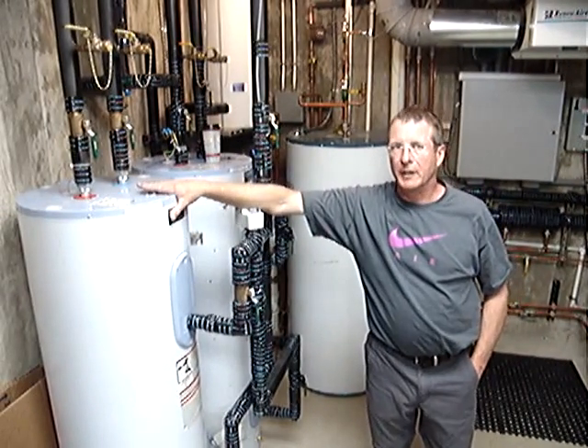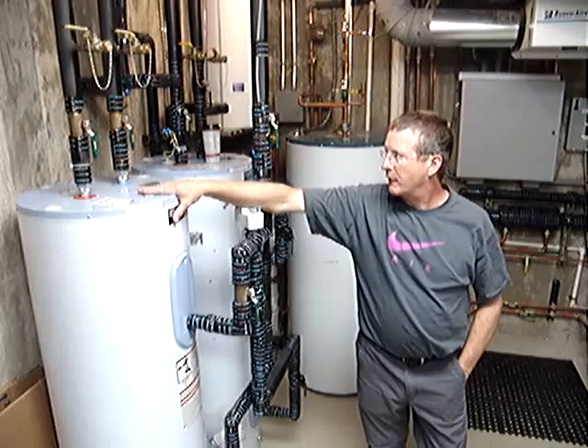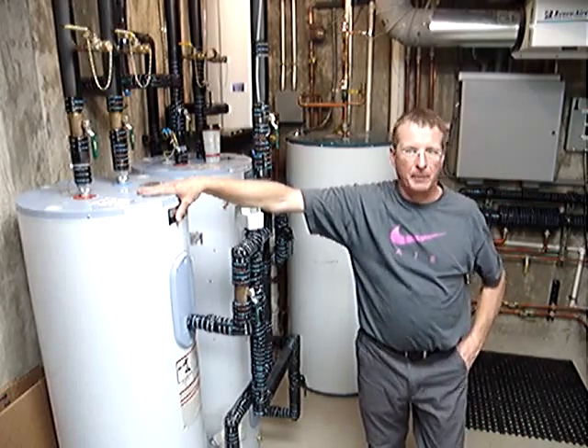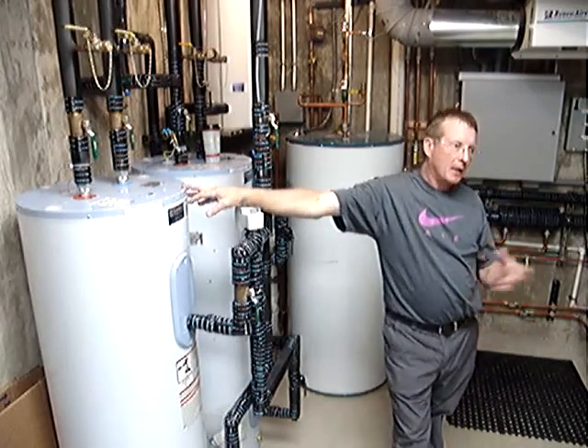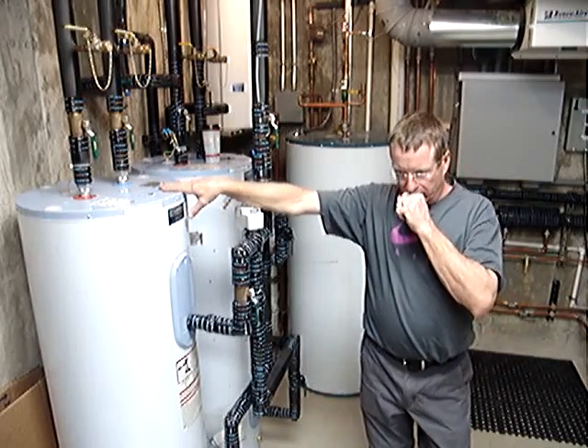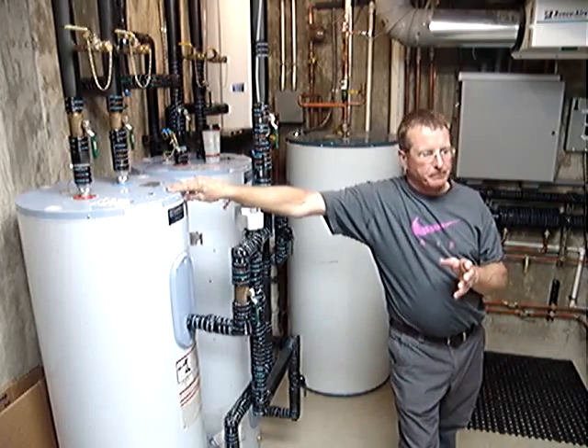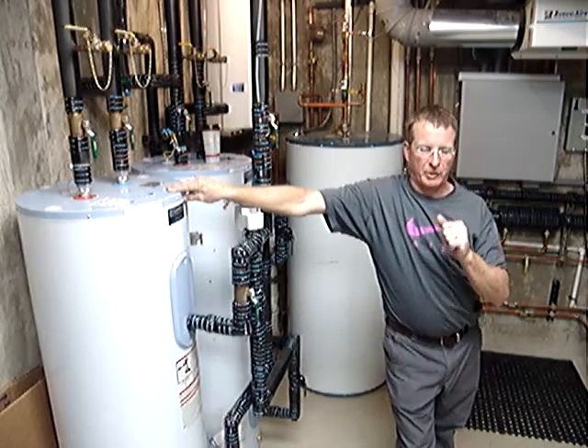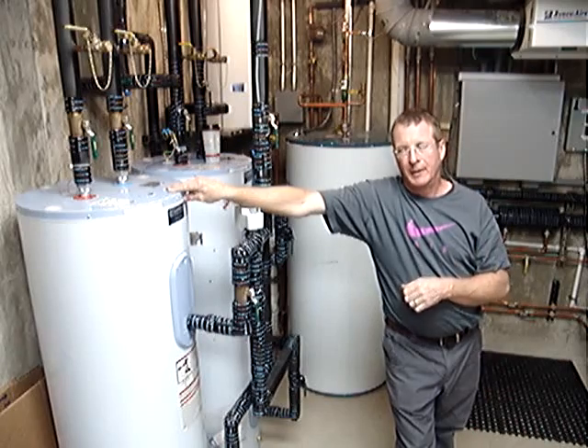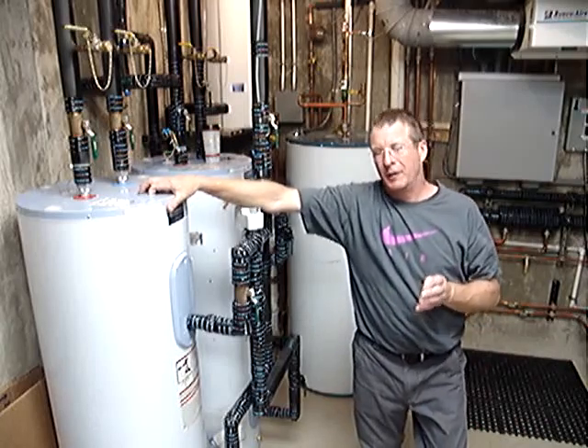basically condense it and store it in this tank over here. This tank right here is our heating buffer tank. From this tank, the water is pumped through the network of tubing in the floors.